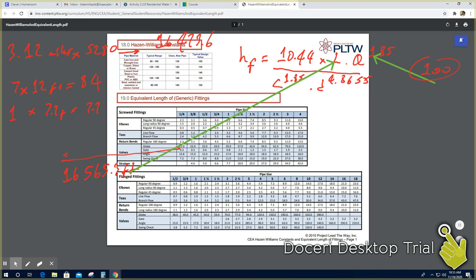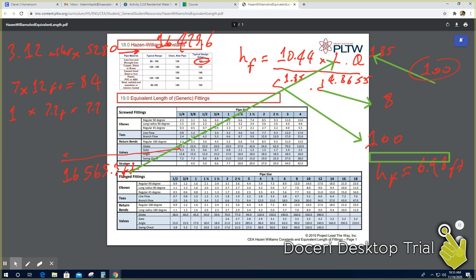C is 100 because the material is cast iron — you can verify this from the provided table. The pipe diameter d equals 8 inches. Plugging all values into the Hazen-Williams formula gives hf equals 6.98 feet. That's the answer for B.